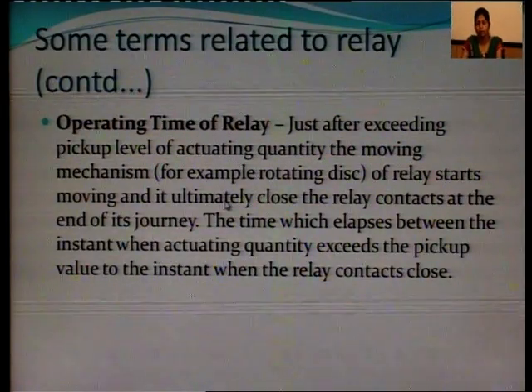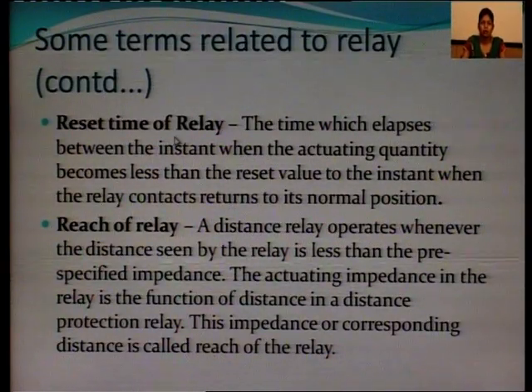that time is known as operating time of the relay. Now next is reset time of the relay, the time which elapses between the instant when the actuating quantity becomes less than the reset value to the instant when the relay contacts return to their normal position. So this is known as reset time of the relay. The next is reach of the relay. A distance relay operates whenever the distance seen by the relay is less than the pre-specified impedance. The actuating impedance in the relay is a function of distance in a distance protection relay, and the impedance or corresponding distance is called the reach of the relay.